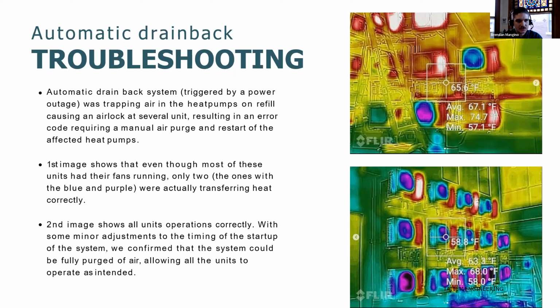The way we address that is that we have a way to alert the staff that there was a drain back operation, which is just one of those leak detection systems that'll send a text message to your phone, and then we'll have the staff go and walk around and verify that the systems are operating properly when we do have a drain back. One thing we did verify over the course of the winter is that if we had a heat pump that would go out on an error code during a drain back operation, they would not freeze when sitting in the error code because we would have enough thermal energy drifting through the lines.